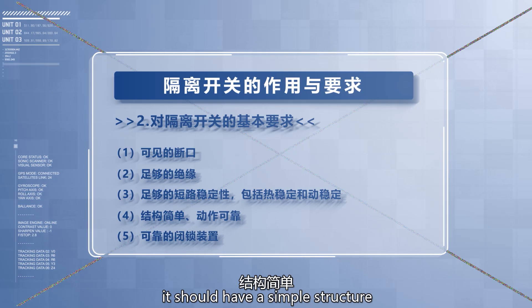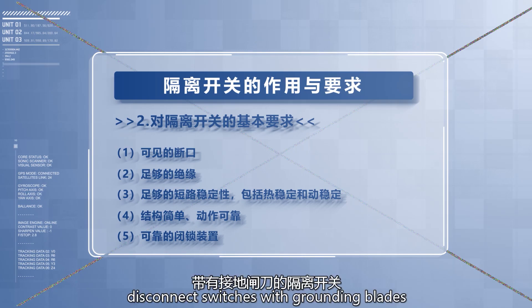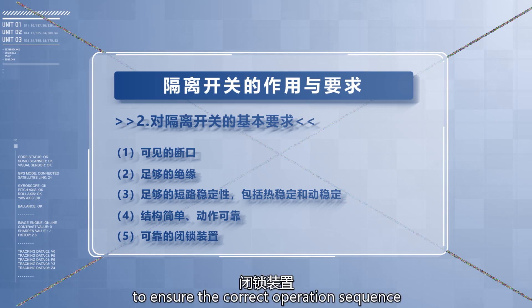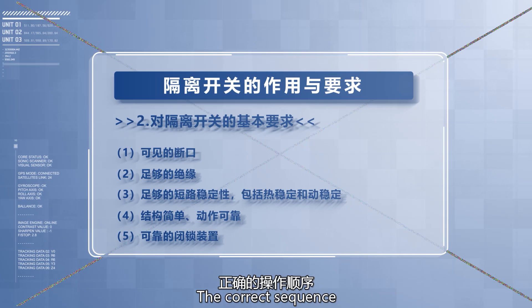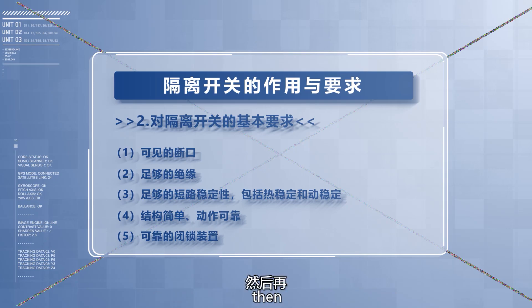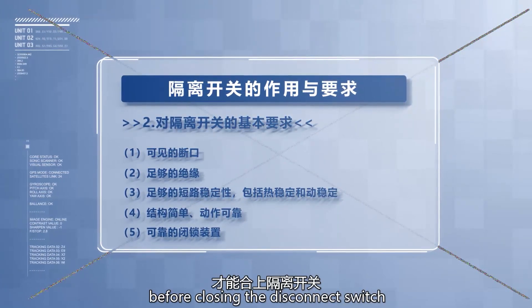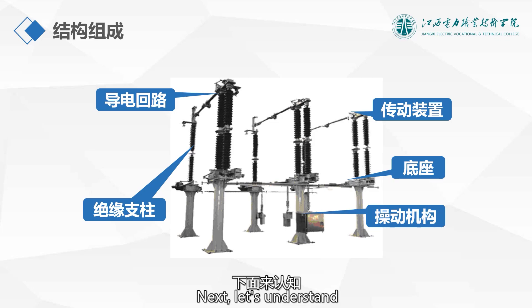Fourth, it should have a simple structure and reliable operation. Fifth, disconnect switches with grounding blades should have interlocking devices to ensure the correct operation sequence. The correct sequence must be to open the disconnect switch first, then close the grounding blade, or to open the grounding blade first before closing the disconnect switch.